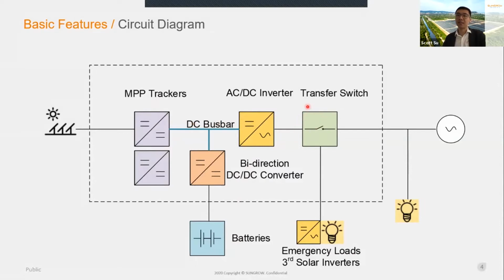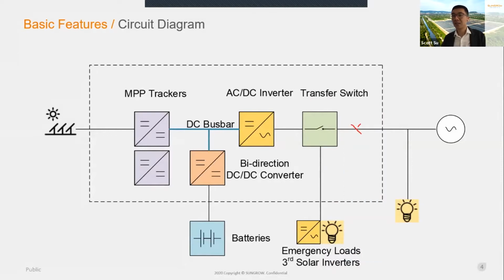The last circuit is the transfer switch. You can see it has 2 AC terminals. Here we connect to the emergency loads and the third-party solar inverters. And here we connect to the grid. So what's the function of that? This transfer switch can disconnect the grid when the grid has a power outage, and then the system can still generate the power to supply the emergency loads. Okay, so this is the backup capability, and we have the seamless transfer.